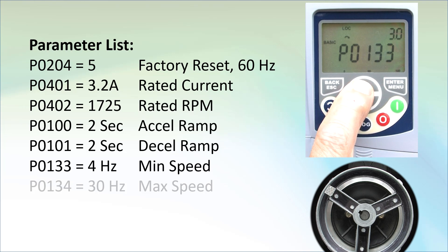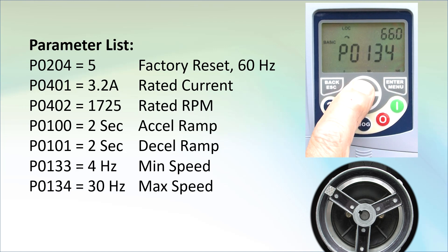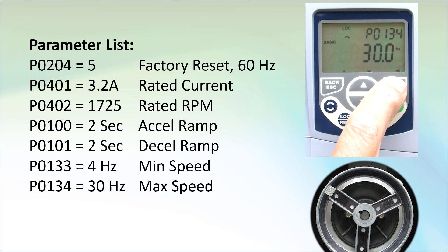Parameter 133 is the minimum speed parameter. Let's make that 4 hertz just to be different. Enter to accept. Parameter 134 is the max speed. Let's limit that to 30 hertz. Enter to accept.